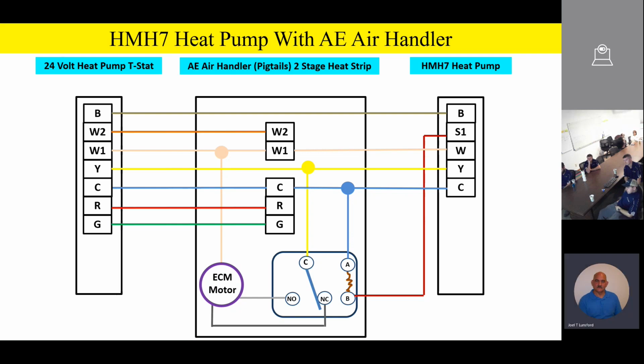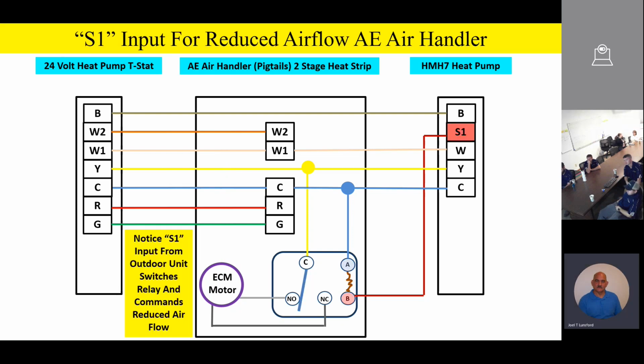So let's go ahead and animate this real quick for you. As you're taking a look at it, watch carefully. When the outdoor unit reaches about 60 to 65% capacity, bang, it's going to energize an output on that S1 output. It'll energize the relay, and you'll notice it's going to switch the relay to our normally open contact now, and it's going to feed power to the ECM motor on the reduced airflow tap. So again, we want that to be about 60%.